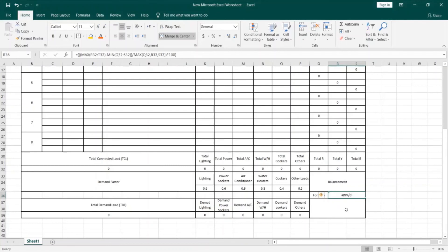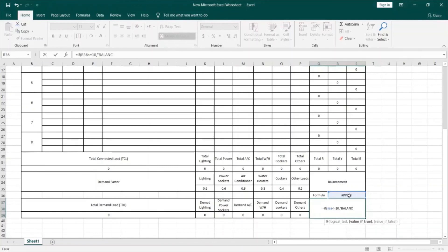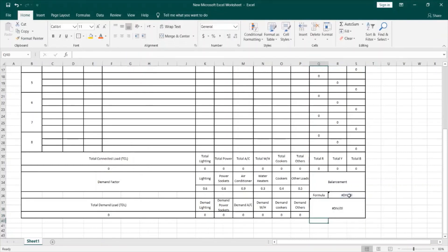Now, I will define the cell that will indicate if the DB is balanced or not. It will use an IF statement: if this formula value is less than or equal to 10, then I want to see the word 'Balanced,' otherwise 'Unbalanced.' I will close the bracket and press enter. If you have taken a C++ or programming course, you will be familiar with the IF statement and how it works. Now, let's make a trial and identify some loads to see if this schedule is actually solving these calculations.